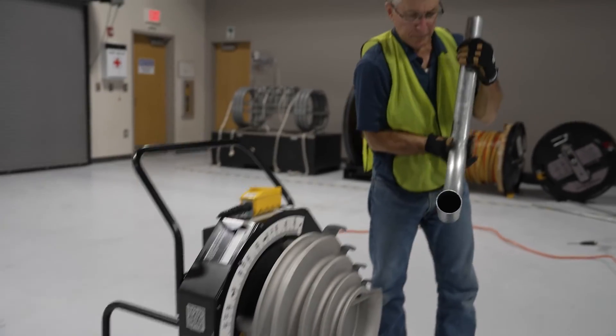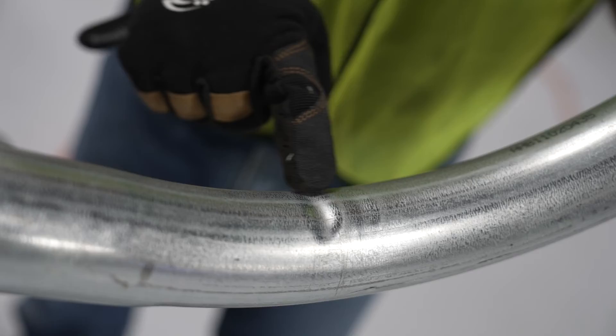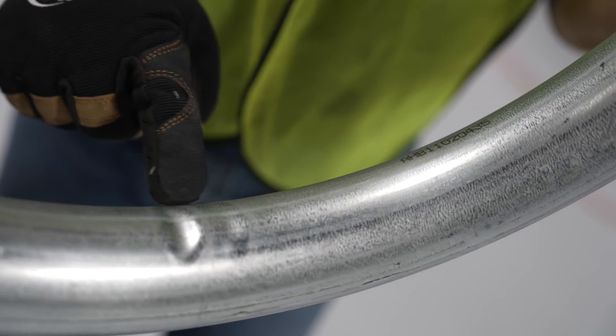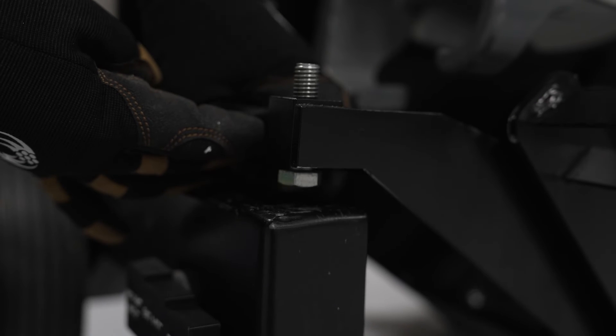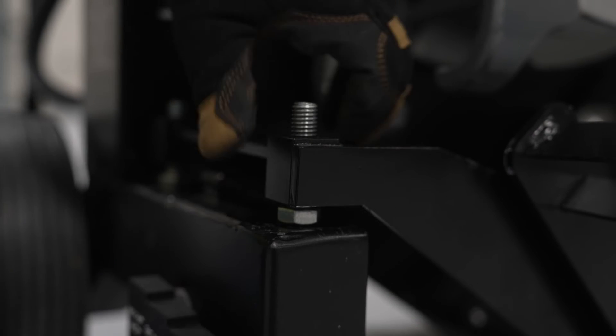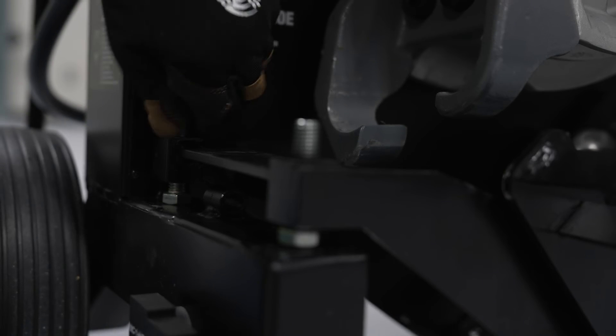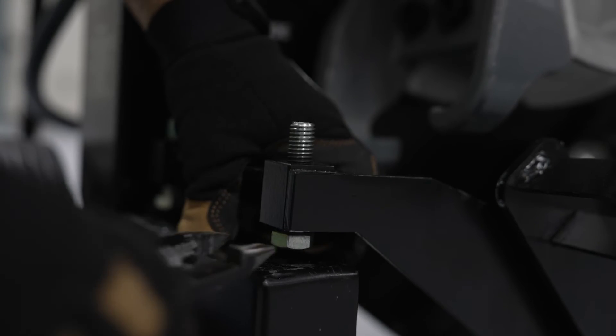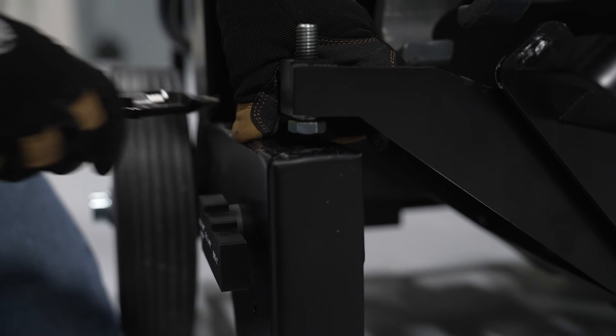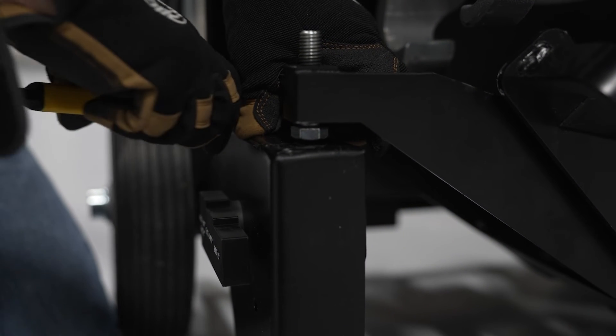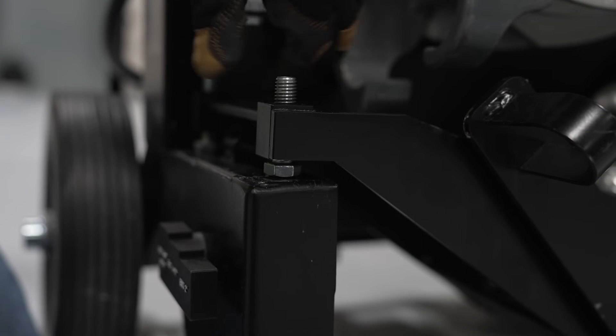Now depending on the brand of conduit that you're using, you may see some undesirable defects in the bend. If you see kinks in the conduit like this, that means that the pressure roller squeeze was not set high enough. To correct it, you need to increase the pressure or the squeeze on the conduit, and to make that adjustment, you need to raise the height of the pressure rollers. So simply loosen the set screws on the top of the roller arm, turn the hex bolts a half a turn clockwise—that'll raise the rollers—and then retighten the set screws and try another bend.